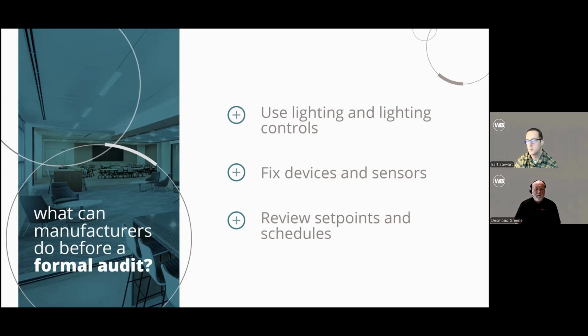So before you get into the audits, if you want, just go on a Monday morning and take a look at what you can do in terms of adjusting set point schedules. We always encourage, for want of a better phrase, that you can experiment with your building. I wouldn't recommend that you do it on the hottest or the coldest day of the year, maybe a shoulder season like around now. See what happens when you change set points.